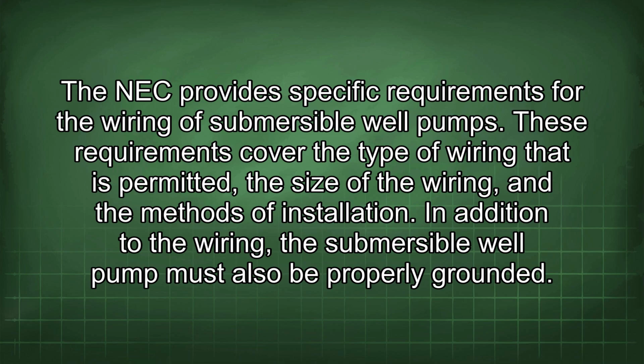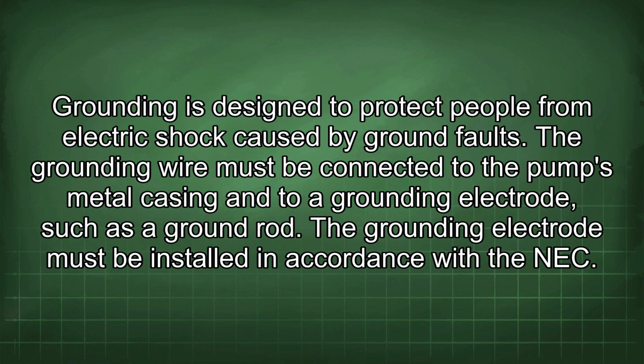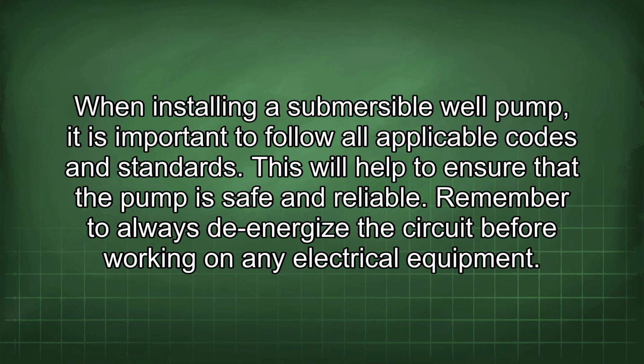In addition to the wiring, the submersible well pump must also be properly grounded. Grounding is designed to protect people from electric shock caused by ground faults. The grounding wire must be connected to the pump's metal casing and to a grounding electrode, such as a ground rod. The grounding electrode must be installed in accordance with the NEC. When installing a submersible well pump, it is important to follow all applicable codes and standards. This will help to ensure that the pump is safe and reliable.